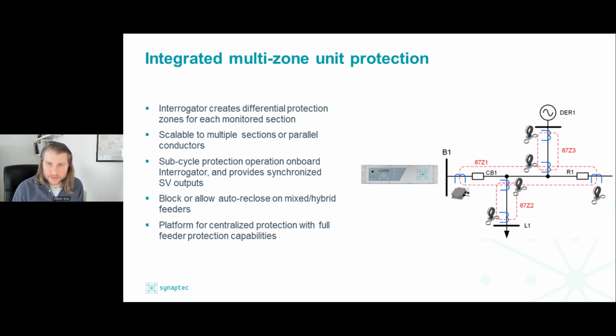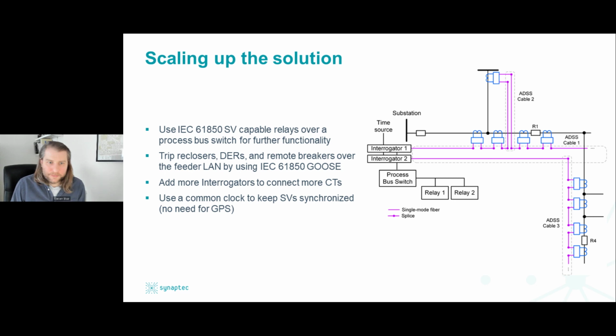In general, the solution is building towards a centralized feeder protection platform where all of the remote measurements are available back at the substation, and good decisions can be made to protect every aspect of that feeder. The solution is also very scalable and flexible. A simple deployment could start with just one key zone. Even adding a few remote CTs can provide a pretty good payoff by greatly improving the protection speed and sensitivity. Then that can expand over time to add more functionality and provide more granular fault detection zones, as Bogdan explained earlier.